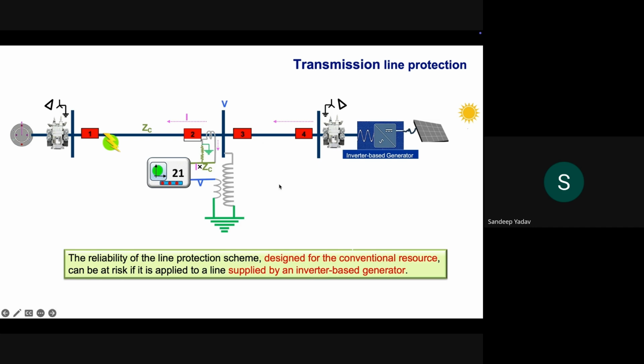These relays have been developed and designed over the period of time keeping these synchronous generators in mind. Now that the fault behavior of these inverter-based resources has changed considerably from the conventional sources, the reliability of the distance protection, of the line protection, and other protection schemes in general needs to be looked into, and their reliability for all kinds of fault, for weak sources, for strong sources, grid side or the inverter side, they all need to be looked into to ensure that the fault is cleared in minimum duration and it is not prolonged for a long period of time.